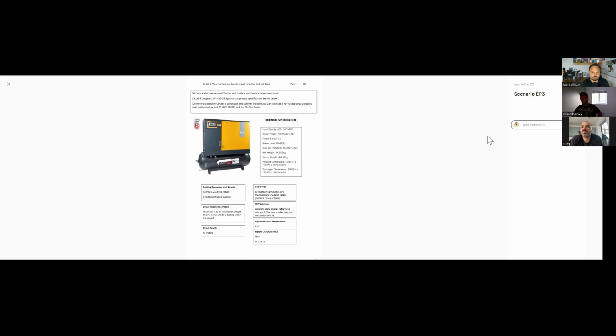A bit on power factor. What's that all about, Craig? So power factor is basically a correction to bring us closer to unity. It's your measure between your true power and your apparent power, which you would have covered in your science and principles for your installation. But we need to effectively balance the loads as best as we can throughout the installation and make sure that it's running the way it should be. And therefore, when you have 3 phases, they're not all running in the perfect pattern with each other. So you can use power factor to bring that much closer to how you want the system to be operating.